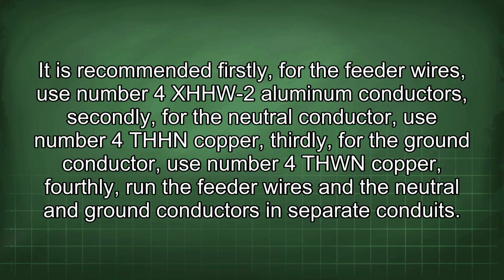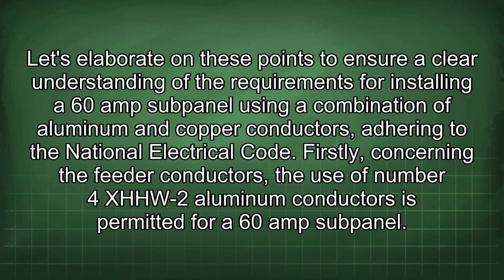It is recommended, firstly, for the feeder wires, use number 4 XHHW-2 aluminum conductors, secondly, for the neutral conductor, use number 4 THHN copper, thirdly, for the ground conductor, use number 4 THWN copper, fourthly, run the feeder wires and the neutral and ground conductors in separate conduits. Let's elaborate on these points to ensure a clear understanding of the requirements for installing a 60 amp subpanel using a combination of aluminum and copper conductors adhering to the National Electrical Code.